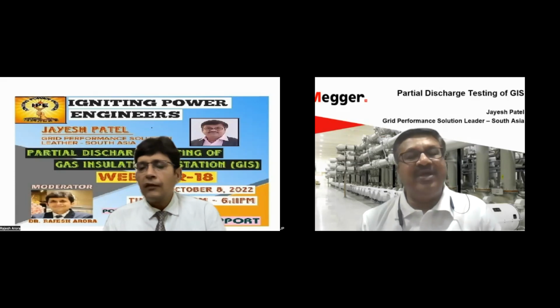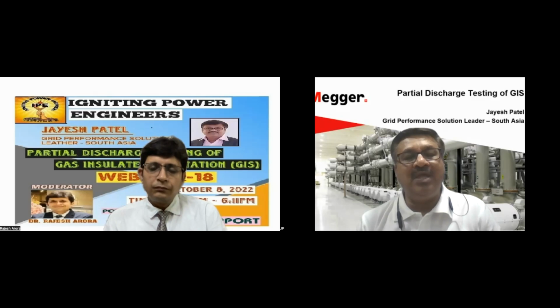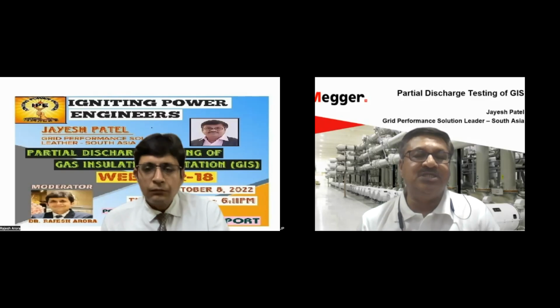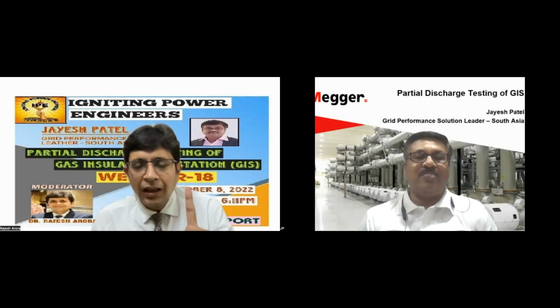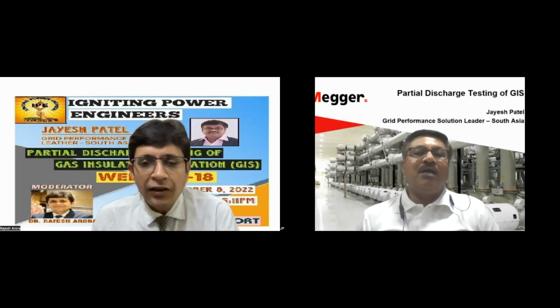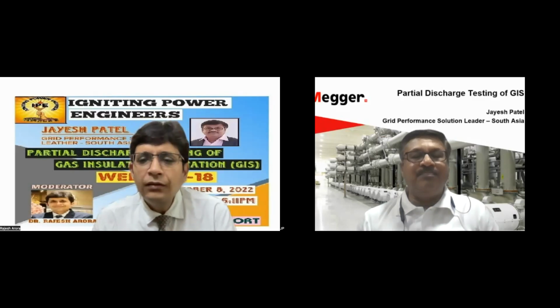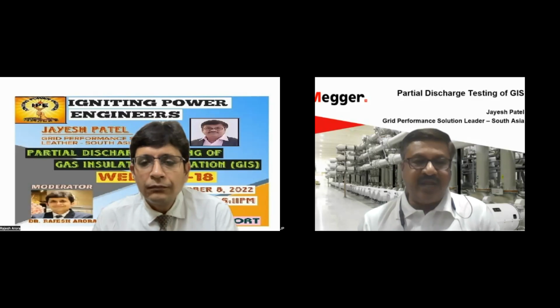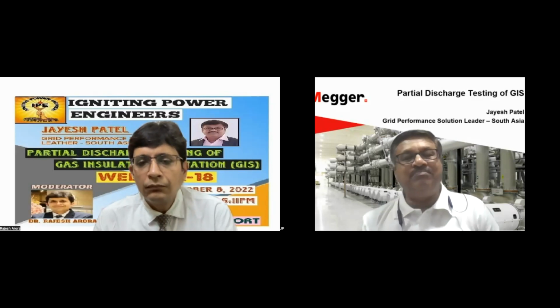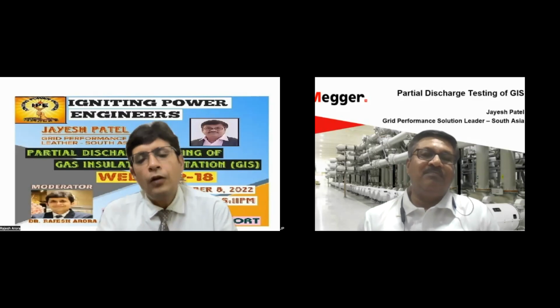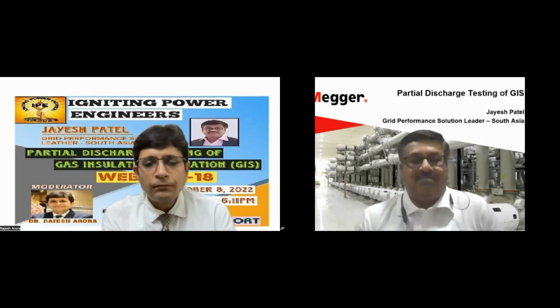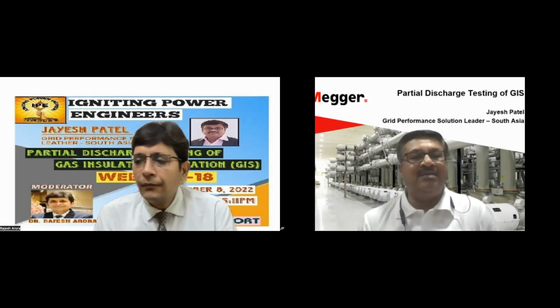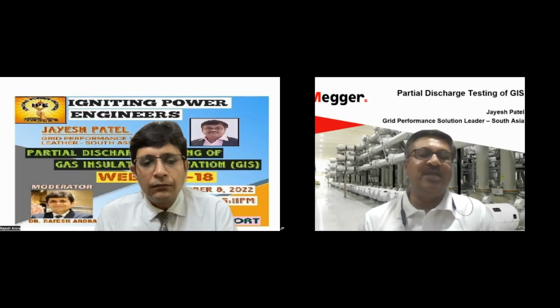The second imperfection is during the commissioning, or maybe during evacuation and filling of SF6 gas. If proper care is not taken, then some dust particles, some metallic portions can get inserted into this GIS. So this is another imperfection. What about the transportation? My question was related to transportation. Transportation, if it is an imperfection, that could typically be a loose connection, and that can be easily captured or addressed during HV commissioning. Okay. Because during HV commissioning, if they are visible, then you can always open again, take care of them, and you can still go away with that.